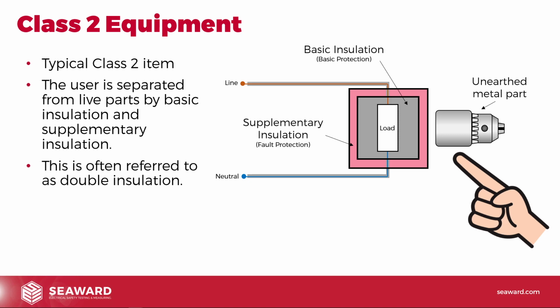for its safety. So with class 1 equipment, if that earth goes, you've lost that earth contact. If that earth connection hasn't been made, or it gets dirty, or there's a bad connection, you've lost your fault protection. Whereas it's very hard to lose a second layer of insulation. So almost with class 2 equipment, the safety is built in. You're not relying on the resistance of the earth connection.